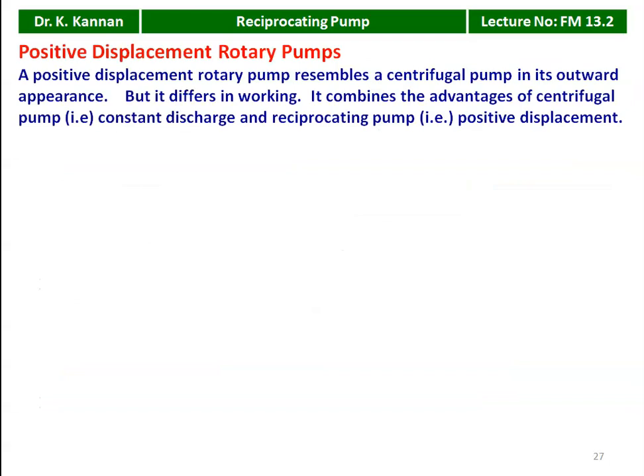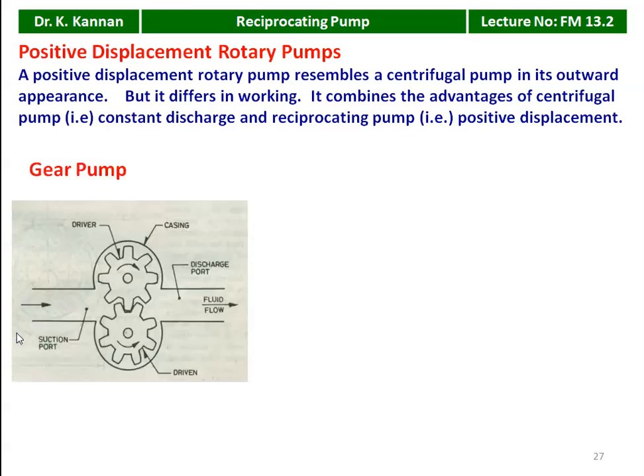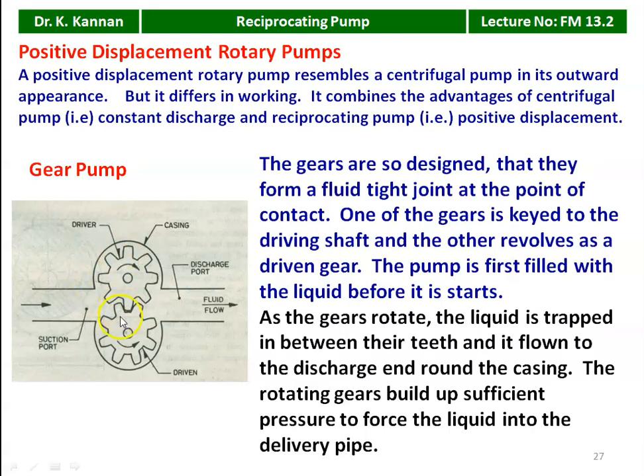Next, we discuss the positive displacement rotary pump. It resembles a centrifugal pump in its outward appearance but differs in working — it combines the advantage of the centrifugal pump (constant discharge) and the reciprocating pump (positive displacement). There are three types: gear pump, vane pump, and lobe pump. In the gear pump, there is a driver gear and a driven gear, with a suction port and a delivery/discharge port. The gears are designed to form a fluid-tight joint at the point of contact, so there is no leakage through the gear contact.